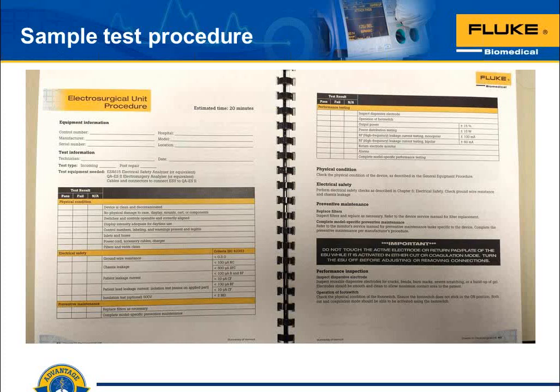So we would use something called the power distribution test that you'll find on the QAES2, which is our top-of-the-line electrosurgery unit analyzer these days. And what it does is it has a form of onboard test automation in which you choose an output power level, you dial it into the ESU, and then when you start the test, the QAES2 will apply that output power across a series of loads that you select, and you'll get a response from that, and it will draw a little curve, a little plot of the output power against the load value over time.